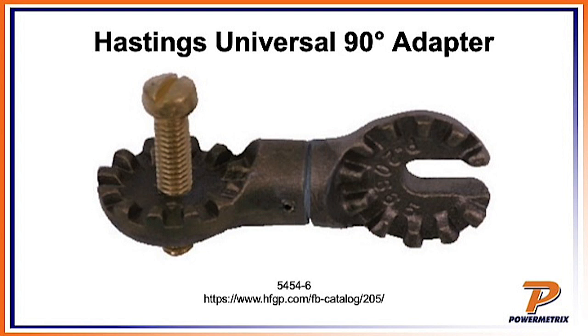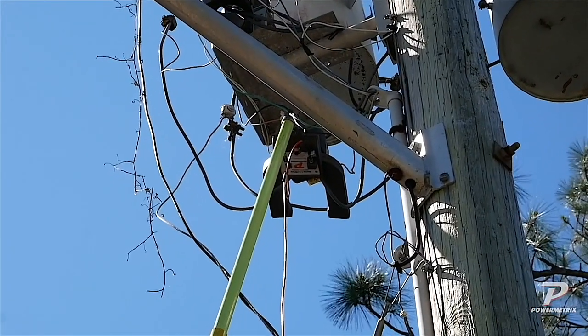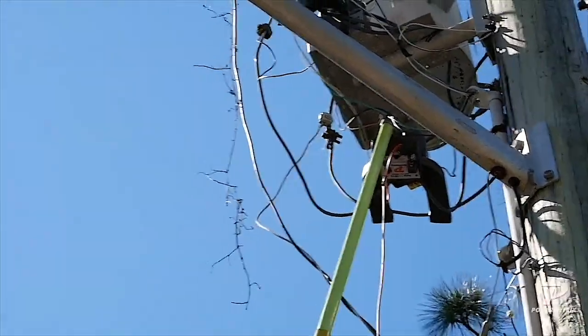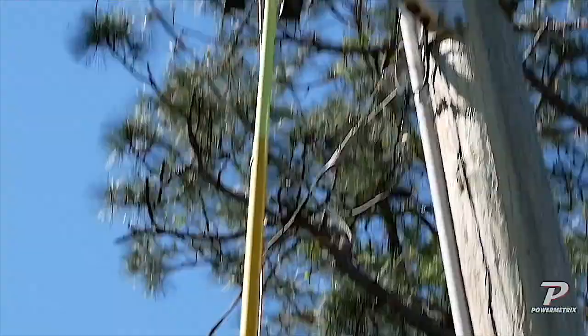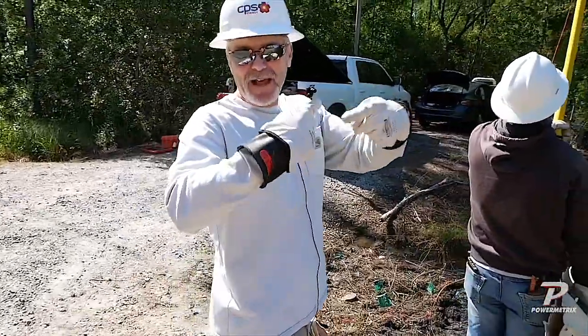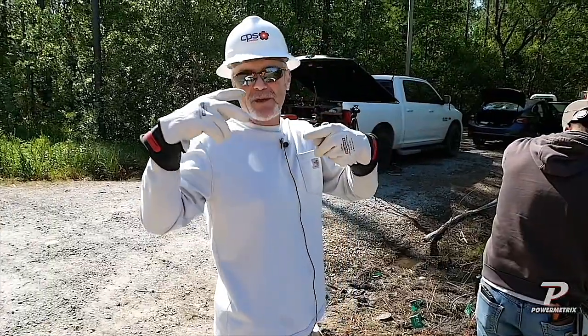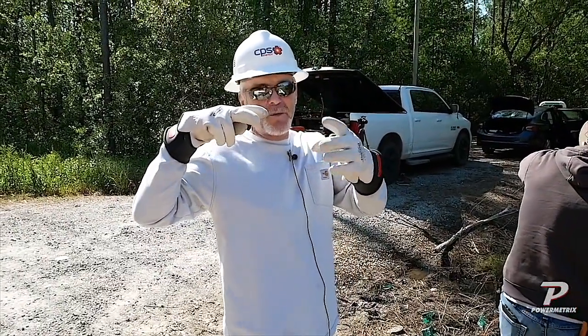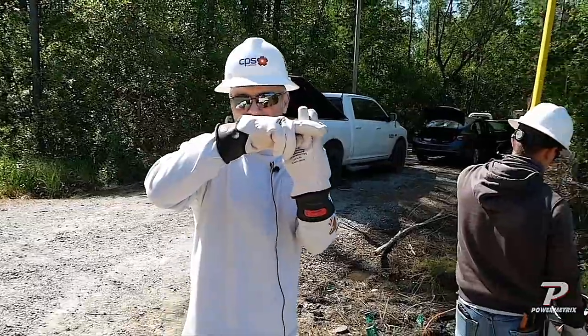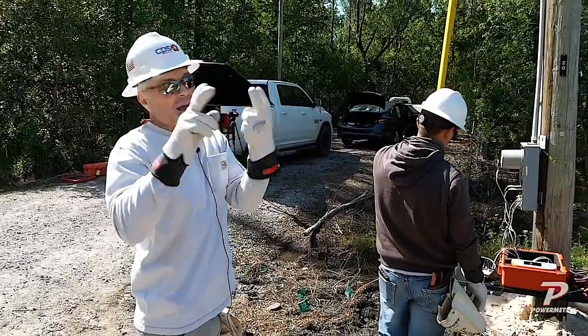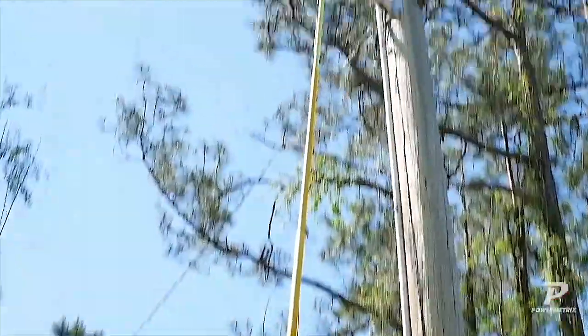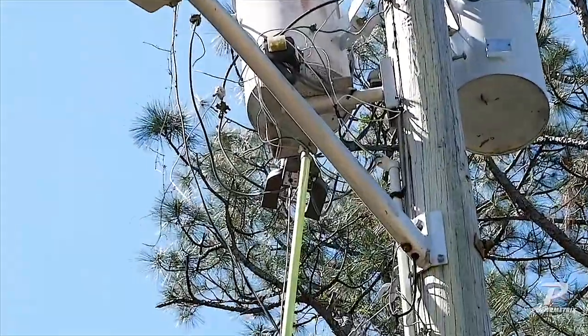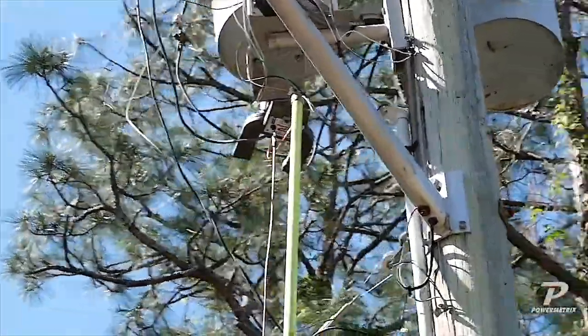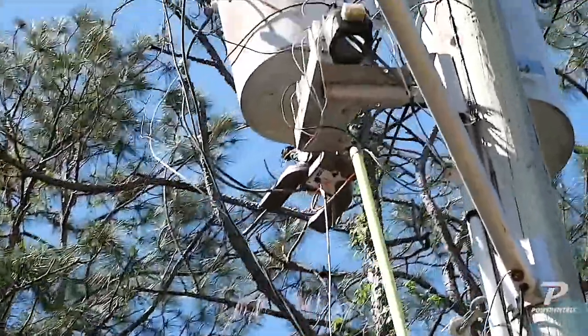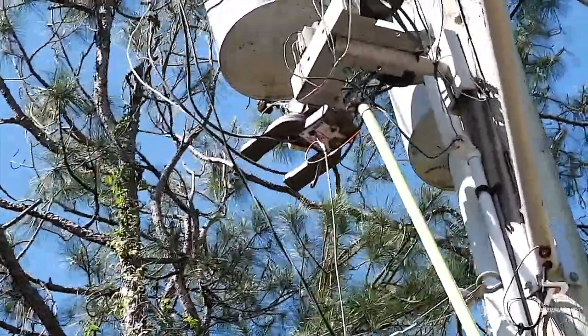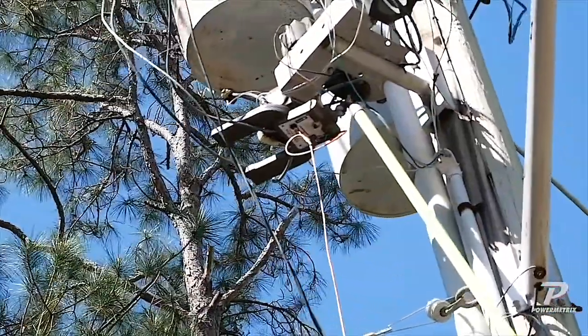Like we said before, when you've got two conductors coming out, if you can grab right there very close to that CT, you'd just use one single loop with your flex. Well, this is that same principle. If we can get right there at the CT, real close to it, we can grab both of those conductors with that high volt probe. With the adapter he's got, laying it flat over like that, he can get in there real close and slide it in. You can see he slid it in really close, and he's grabbed both of those conductors where they're crisscrossed on that left CT. So he's got A and B there, and we're summing them up.